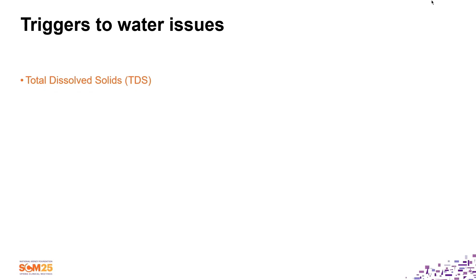Okay, water issue. These are triggers to water issue: total dissolved solids, percent rejection, delta pressure, and hardness. Okay, total dissolved solids is what you read as the quality of your water. Typically, manufacturers, when they send out their equipment and have an IFU, have a top limit of 50 parts per million as their alarm point. Most facilities drop that down so that they set their alarm point at 25 parts per million.